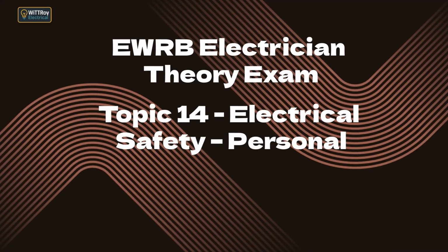14.4 Precautions for circuits with capacitors or stored energy. Capacitors can stay charged even after the power is switched off, so we must treat them as live until proven safe. AS/NZS 3000 says any capacitor over half a microfarad must discharge to below 50 V within 1 minute if rated up to 650 V, and 5 minutes if rated above 650 V.